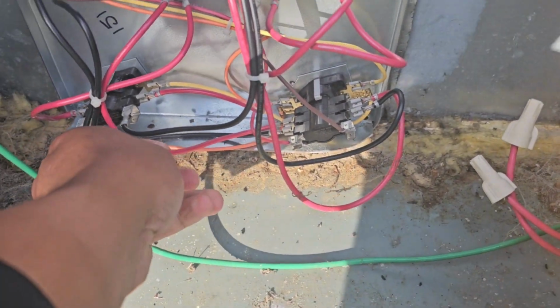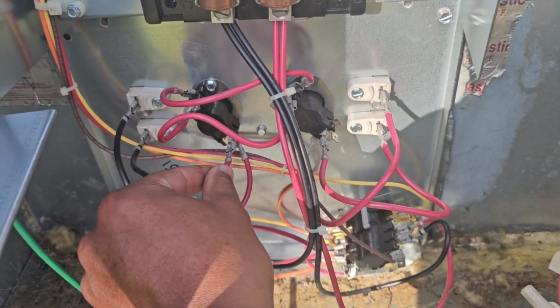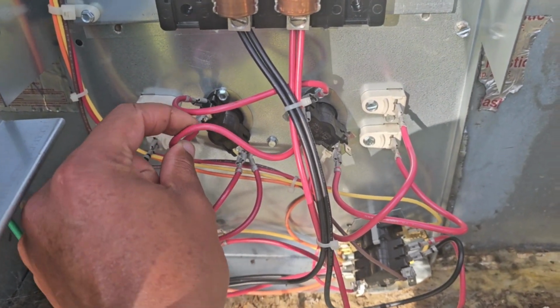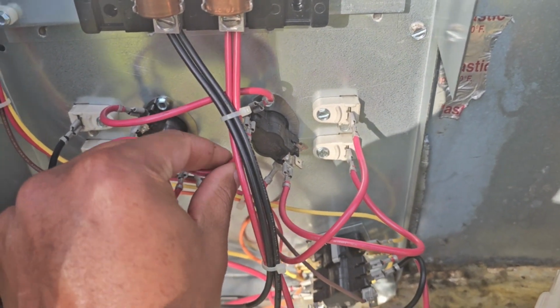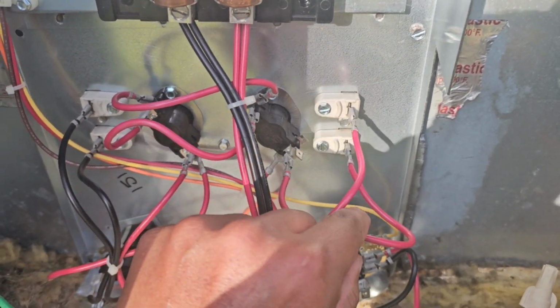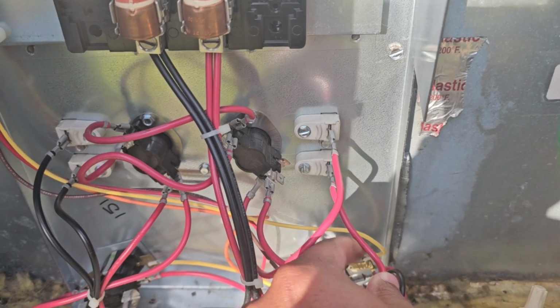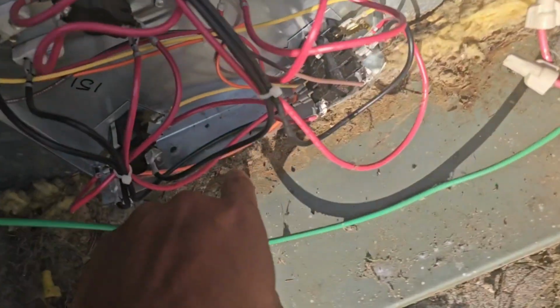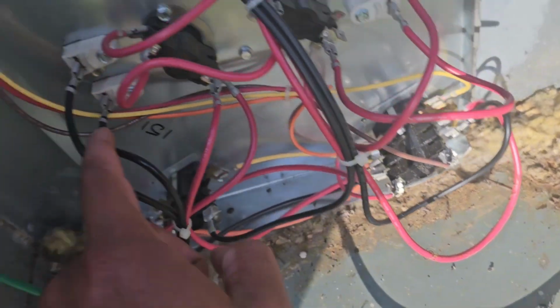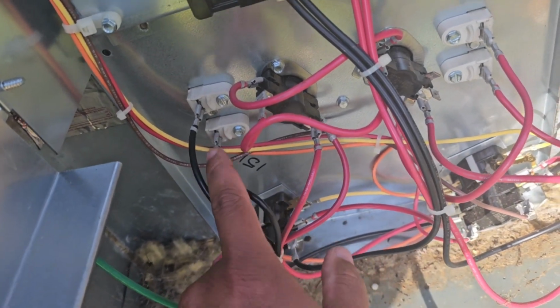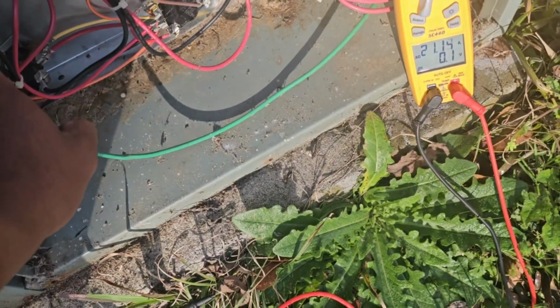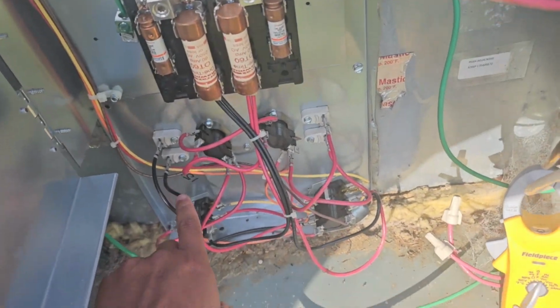If I follow this red wire I was just testing, it goes through what I believe to be the limit switch, comes through here, pops back out, and goes to this leg right here. Whereas the black wire that was on this sequencer comes up and goes to its respective terminal there. So I think I have an issue with the heat strips behind here.